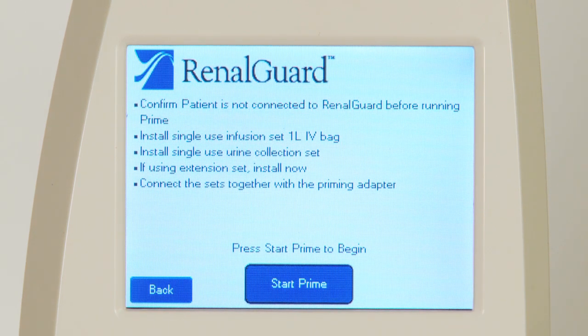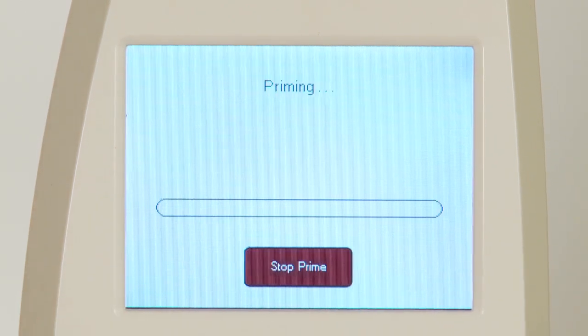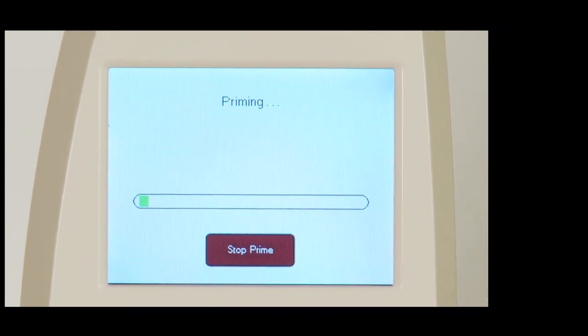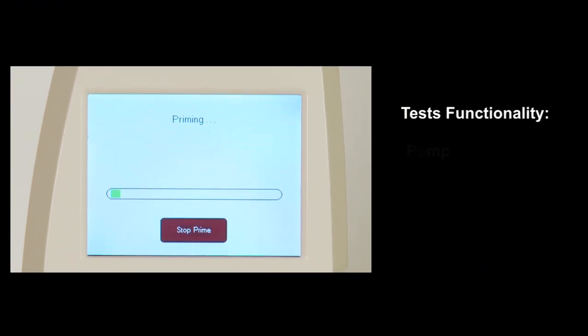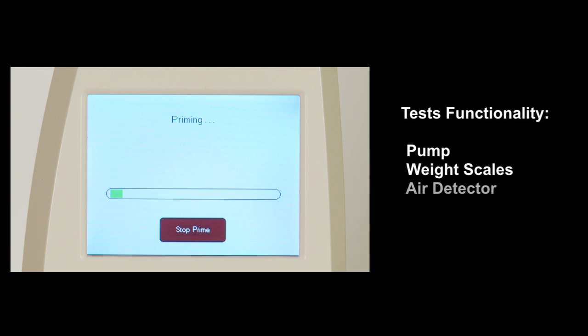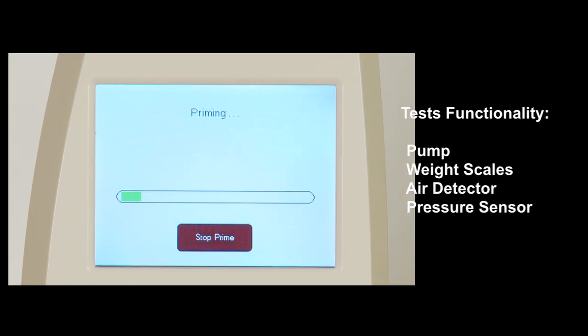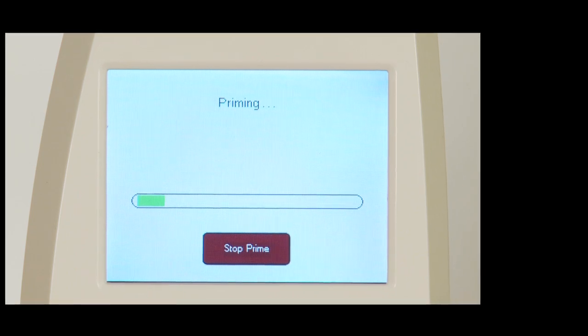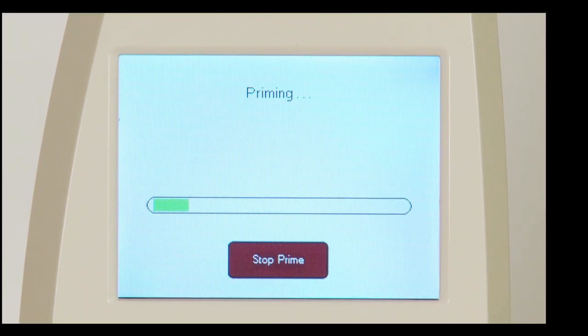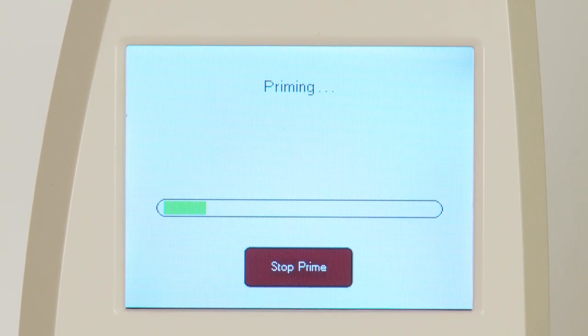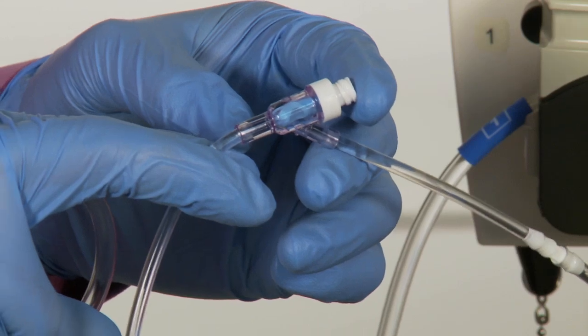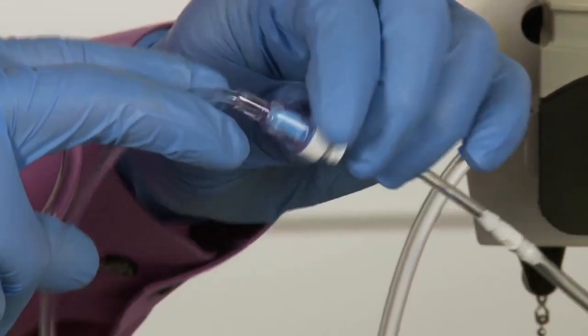As soon as prime starts, you should hear the pump running. Prime performs a number of important functions and takes about 2 minutes. Prime fills the infusion set and urine set with saline and tests all of the RenalGuard's functionality, including the pump, weight scales, air detector, and pressure sensor. During prime, please don't touch either the infusion or urine collection bag, as this may cause the test to fail and have to be repeated. You can tap the set to get out any bubbles that have been trapped.